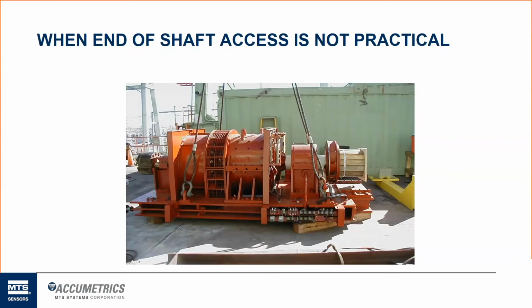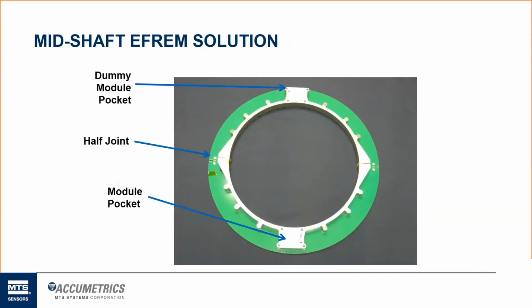So this is typically where we would plan on mounting our next style of EFREM system, which is that midshaft style, and we'll go into more detail in the next few slides. So here's an example of the midshaft EFREM transmitter. It's a two-piece split collar design that has an electronic module on one half, and then a weighted dummy module on the other half that weighs the exact same as the electronic module. It's connected across this half joint here with high strength Unbrako bolts, is how we make that contact, and it's torqued down to each shaft. There's a specific torque rating that will be in every manual, dependent on the size of the shaft as well as the speed of the machine itself.